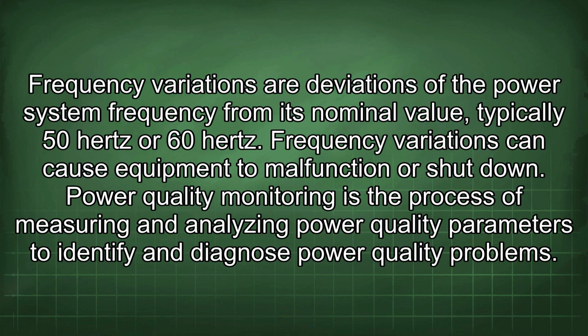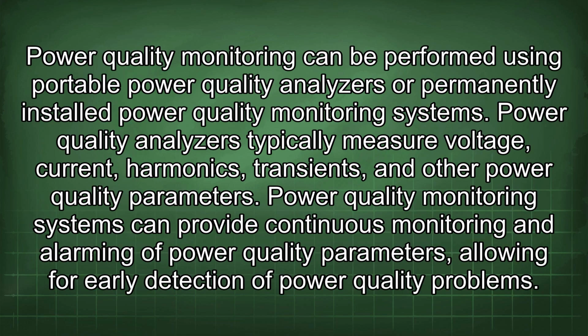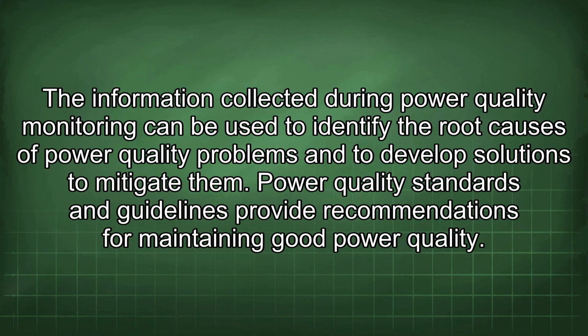Power quality monitoring is the process of measuring and analyzing power quality parameters to identify and diagnose power quality problems. Power quality monitoring can be performed using portable power quality analyzers or permanently installed power quality monitoring systems. Power quality analyzers typically measure voltage, current, harmonics, transients, and other power quality parameters. Power quality monitoring systems can provide continuous monitoring and alarming of power quality parameters, allowing for early detection of power quality problems. The information collected during power quality monitoring can be used to identify the root causes of power quality problems and to develop solutions to mitigate them.